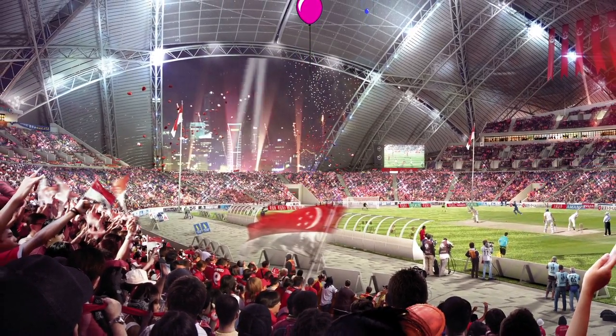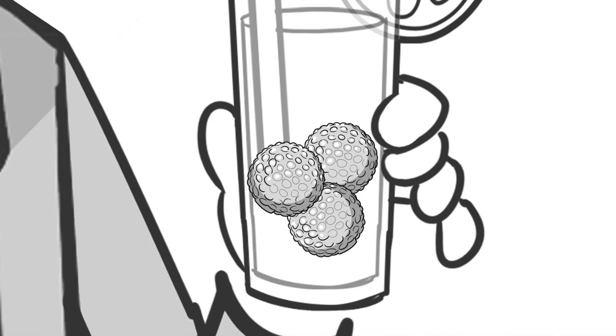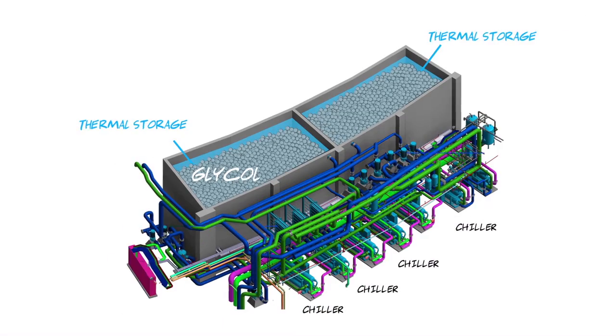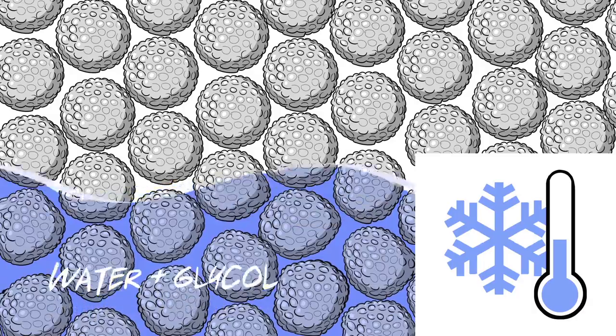Last but not least, for the largest events — like a 10-hour cricket game with 55,000 cheering fans in the bleachers, which occurs only 3 to 4 times a year — we've created an environment-friendly extra cooling system. The solution is a very simple and efficient idea: ice storage technology. You know the plastic ice cubes we use during the summer to freshen our drinks of lemonade? Well, the idea is the same, except on a much, much larger scale. Large tanks containing 1.2 million ice balls full of cooling liquid are located all around the stadium under the tiers. The night before the huge events, we freeze these ice balls in order to obtain 2,000 cubic meters of ice.